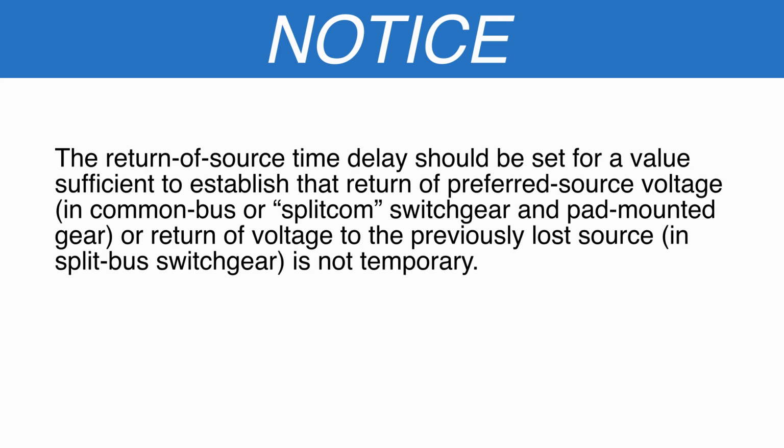The return of source time delay should be set for a value sufficient to establish the return of preferred source voltage in common bus or split-com switchgear and pad-mounted gear, or return of voltage to the previously lost source in split-bus switchgear is not temporary.